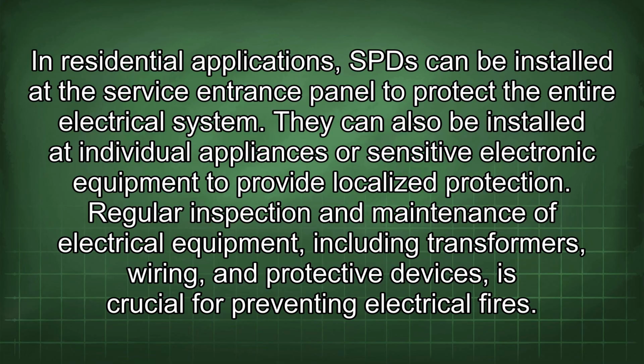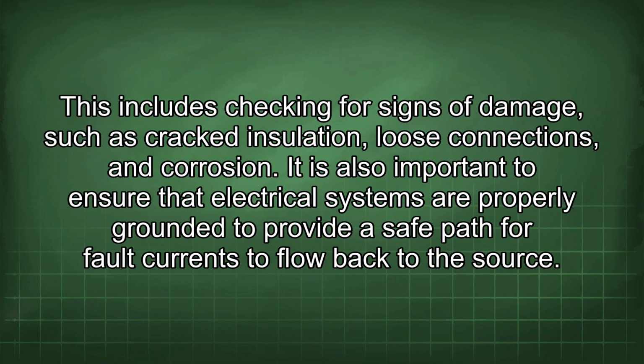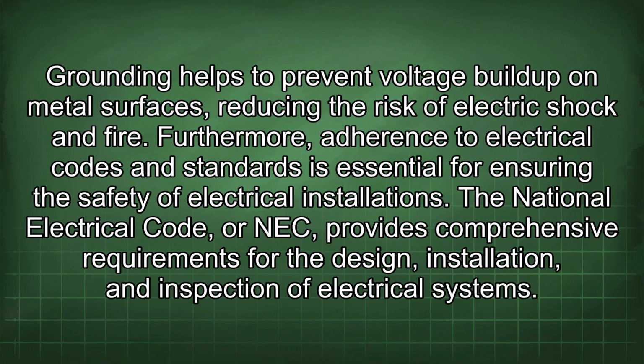Regular inspection and maintenance of electrical equipment, including transformers, wiring, and protective devices, is crucial for preventing electrical fires. This includes checking for signs of damage, such as cracked insulation, loose connections, and corrosion. It is also important to ensure that electrical systems are properly grounded to provide a safe path for fault currents to flow back to the source. Grounding helps to prevent voltage buildup on metal surfaces, reducing the risk of electric shock and fire.